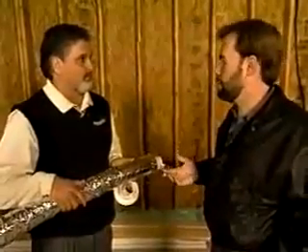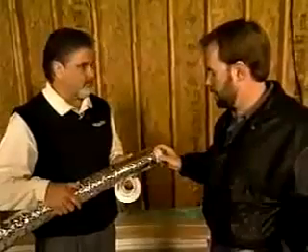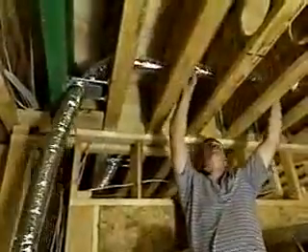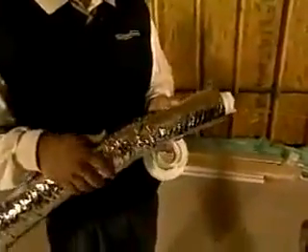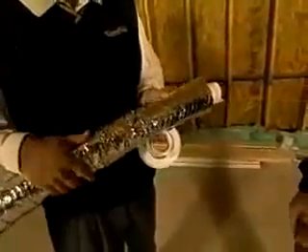So we're going to save money and it's going to feel more comfortable. The ductwork — do you use more outlets in a room than you would with traditional ducts? In a room this size, typically 14 by 14, we'll have two, three, maybe four outlets depending on its exposure. And since it's smaller, it's a lot easier to install in our floor joists. It's easier to go into the floor joists — they can drill those, carry the tube out to the termination point, and carry it into any wall, outside wall, interior, whatever. Since it's so small, we're not going to have to fur out big spaces for it up in the corner of the bedroom or where the wall hits the ceiling. It's in the joist space — it's hidden and out of the way.